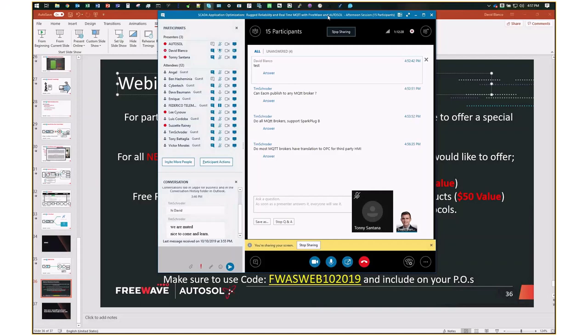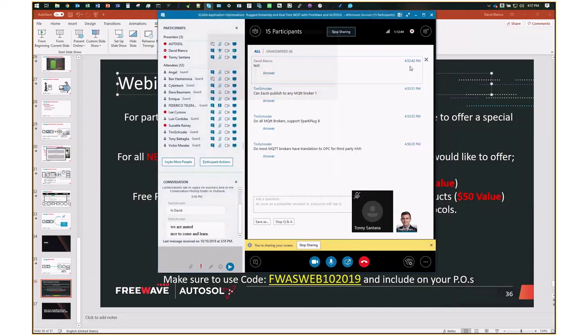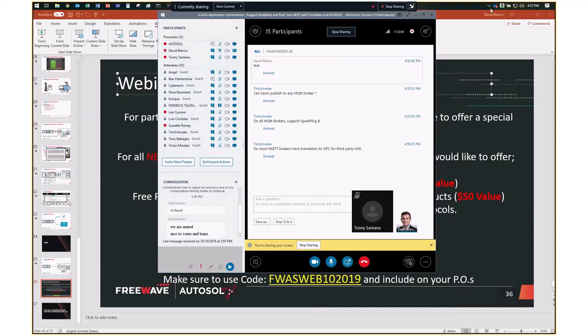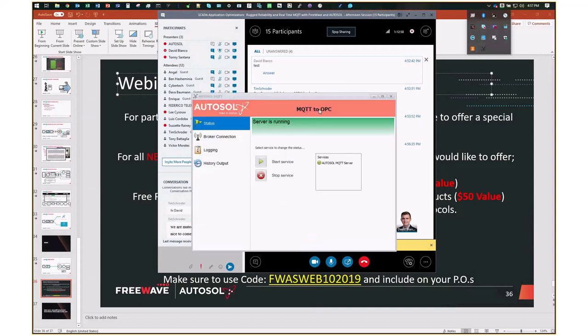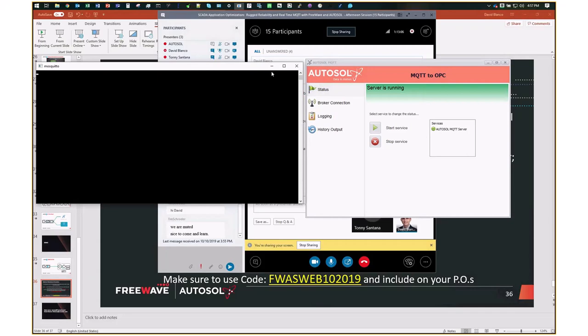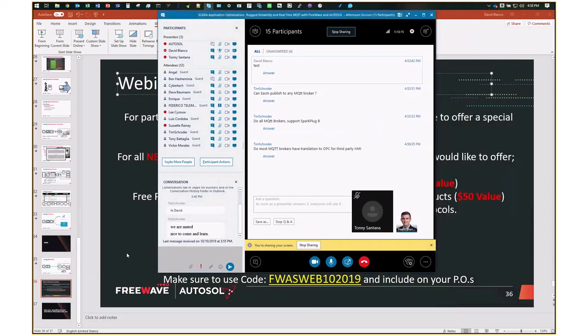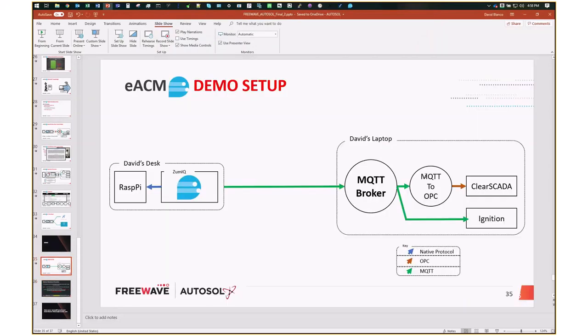Tim asks: Do most MQTT brokers have translation to OPC for third-party HMIs? There isn't one I know of that does that natively. The Mosquitto broker is not translating anything — it's all MQTT. What is doing the translation is AutoSol's MQTT-to-OPC application, which subscribes to the broker and publishes everything as OPC DA for an OPC DA client to consume.